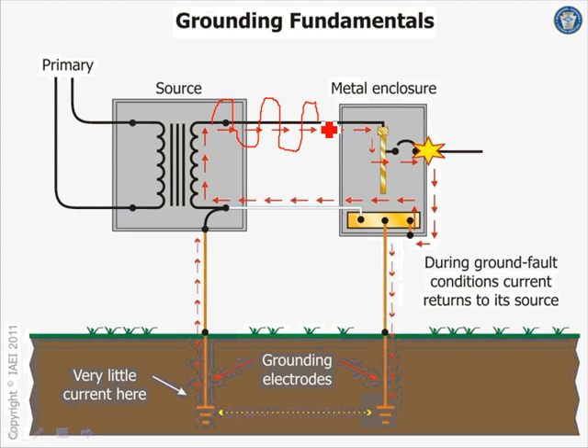So now we got hit by lightning. Look what happened. Now it goes all the way down here, up to the load, and comes back. That's my surge. And see how high the voltage is? Now at this time, with your surge protective device, there's no ground fault, nothing. There's nothing to do with the ground. We don't have a ground fault. We don't have a short circuit. We just have a voltage surge because of lightning or the transmission line.